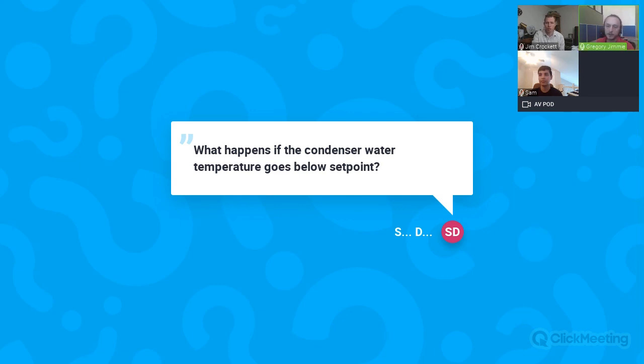There was one that refers to trim and respond to get the ideal condensing water temperature. Generally speaking, I don't think that that's the best way to go about it. I think as cold as you can get it is the better way to do it. The time when you start resetting based on wet bulb or something else, it just creates instability in the system. Let those fans run. I do like the preference of putting a cap on your fans until a certain temperature.